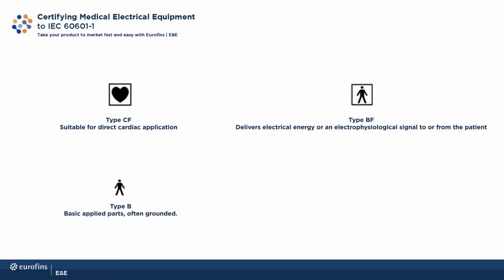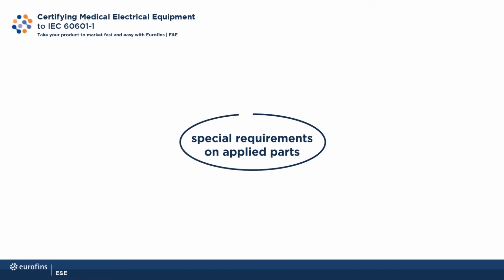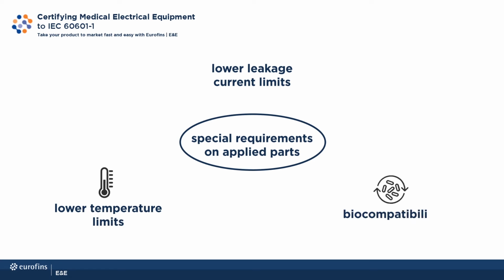If the equipment applies electricity to the human body, it must have sufficient isolation to float. This is the type BF applied part, and everything else can be a type B applied part and may be earthed or have a lesser isolation than a CF or BF applied part. There's also a special category of applied parts, defibrillation proof. These parts will not conduct the current caused by a defibrillation shock to the rest of the body. The standard places special requirements on applied parts: lower leakage current limits, lower temperature limits, and biocompatibility requirements.